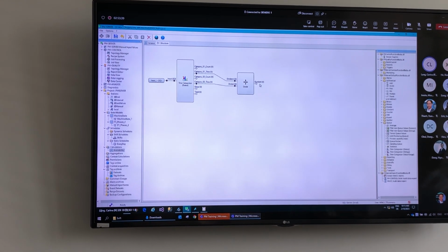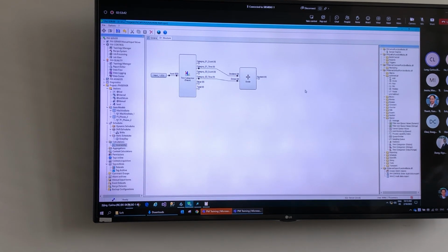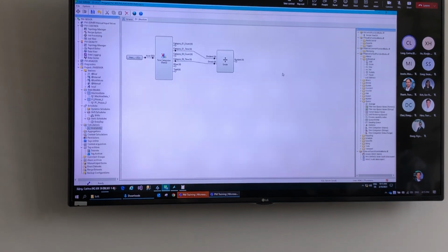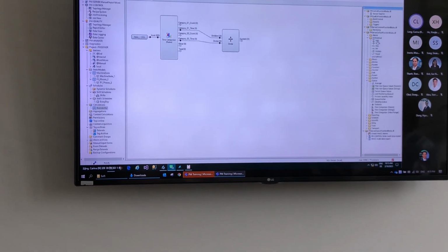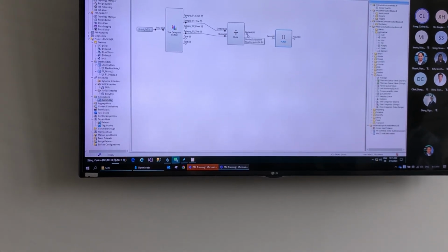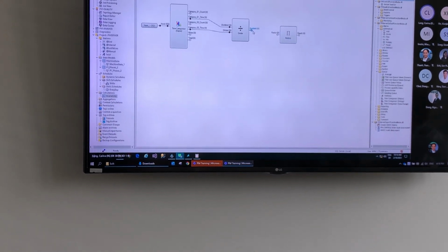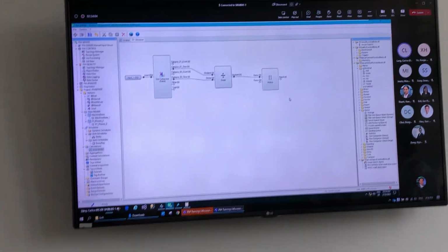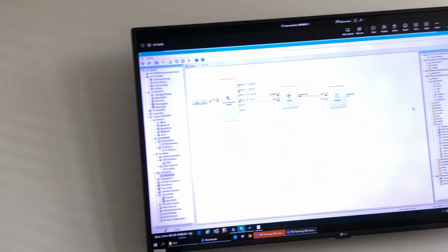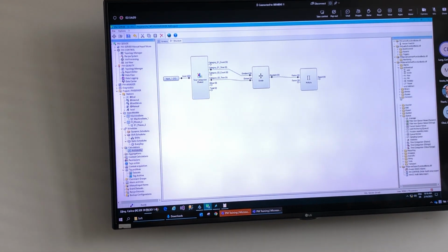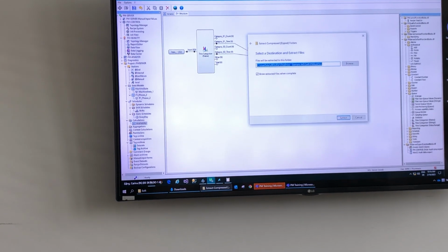So quite simple here, and we do not want to just get the availability because it's a 0 point whatever number. So we want a multiply block, and we want to take the availability, so the result of this division here, as factor 1 of the multiply, and then we want to multiply that one with 100, so we go to constant and add a constant number. And a constant number has two outputs. We can have it as a D word or a double.